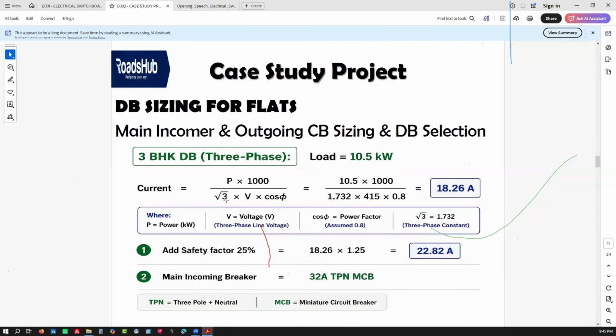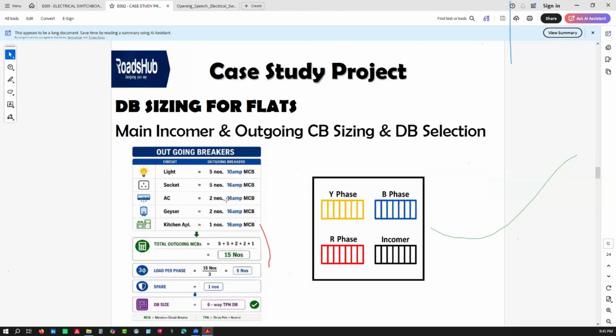So if that's the case, you need now to come up with a sample DB for your three-phase. So remember, you need to have outgoing breakers for the same. But now the trick here, when you add all the breakers that you have for each circuit, if you get 15, a three-phase DB has a factor of 3 because we are supplying with three-phase. So divide 15 by 3, you get 5. You add a spare of 1, you can go for a 6-way TPN DB because that's standard in the market. You see now the difference.